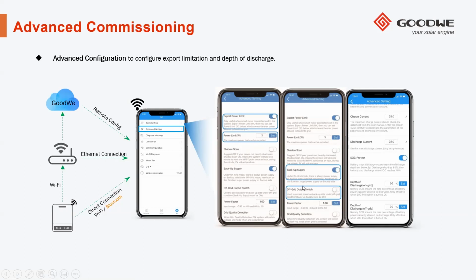We have our backup supply and off-grid output switch. The backup supply will be on by default. If you aren't using the backup and you're only using it as a grid tie system, you can switch that backup supply off to ensure that the backup output is completely off. The off-grid output switch comes on automatically when there is more than one power source available for the inverter. So if you have batteries and solar available, that switch will be on, and when the grid fails, it will continue to function. When there is a problem or an overload or anything like that, the off-grid output switch goes off. If there's only one power source available, it will not come on automatically. It can be manually switched back on, but it is a safety feature to ensure that the batteries and everything are protected and that it doesn't over-discharge your batteries.